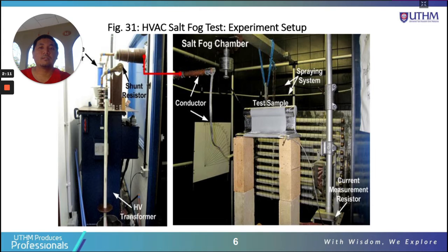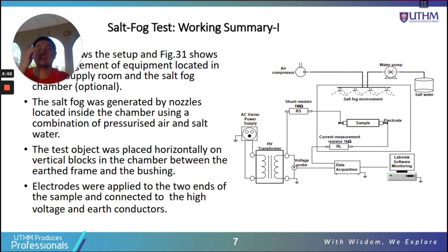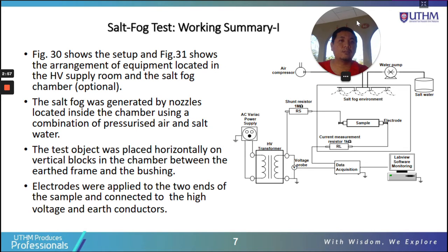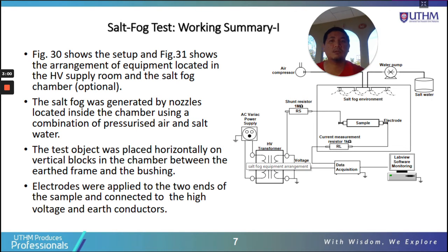Let's look at the actual picture of the salt fog test. Okay, HVAC salt fog test. You can see here that the supply injected is a high voltage AC supply. Same thing, we have a transformer here to supply that HVAC, connected to the electrode here, and then we have the test sample, the electric material that we want to test, and the electrode on the other side connected to the ground. And you can see here the hose that will spray that salt fog condition.